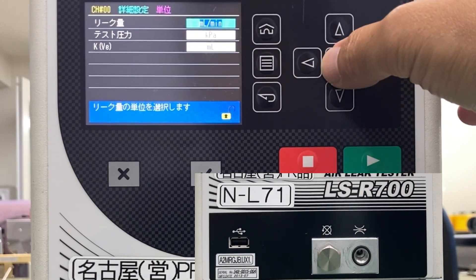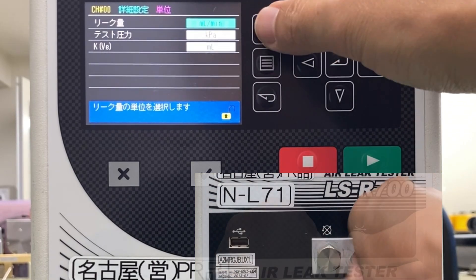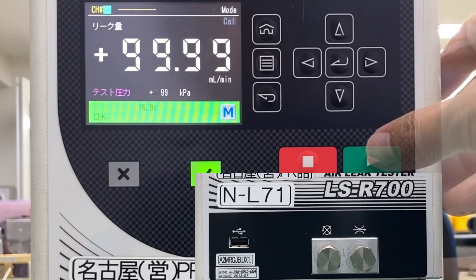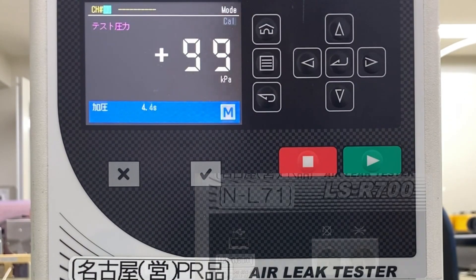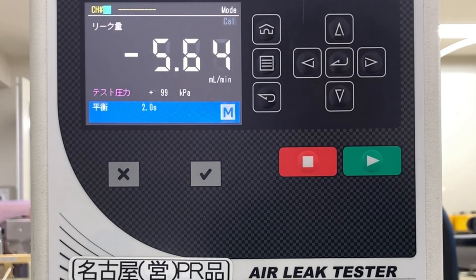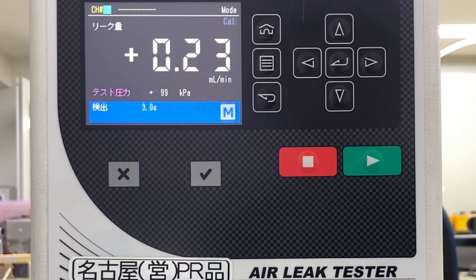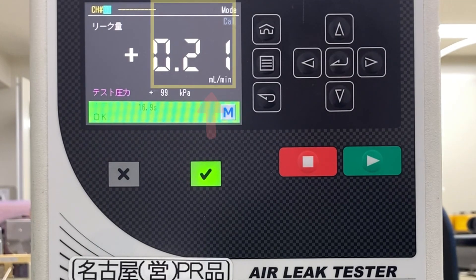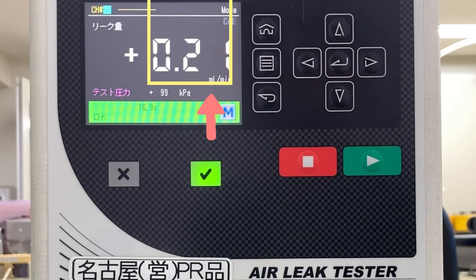Remove the leak master from the calibration port and connect the plug firmly. Press the Start key to start the leak test. The unit was confirmed to be a flow unit, and this work was found to have a leak of 0.21 mL per minute.